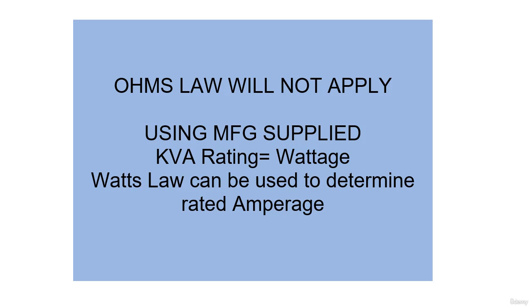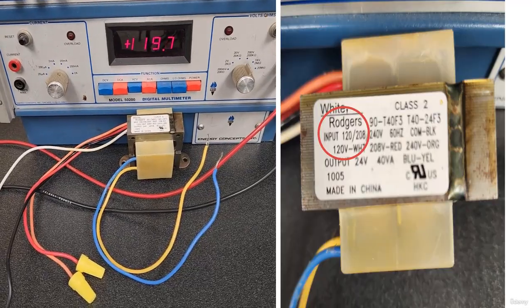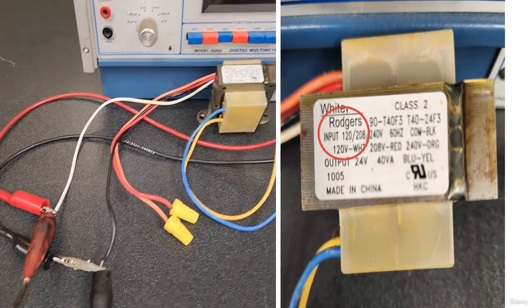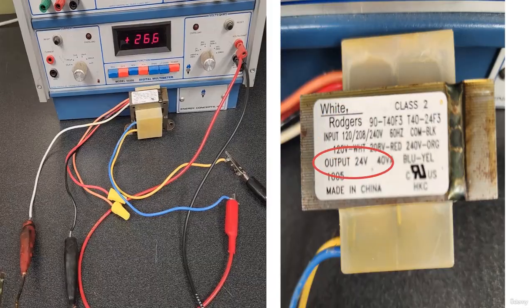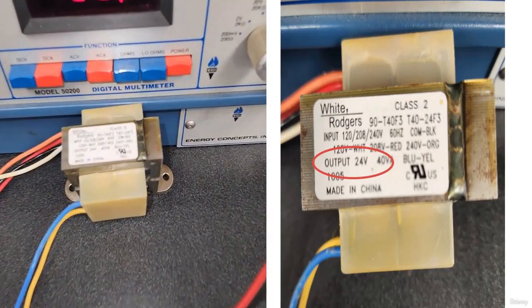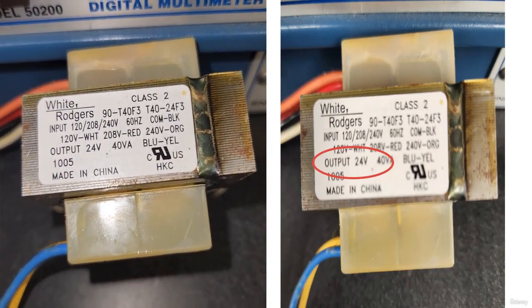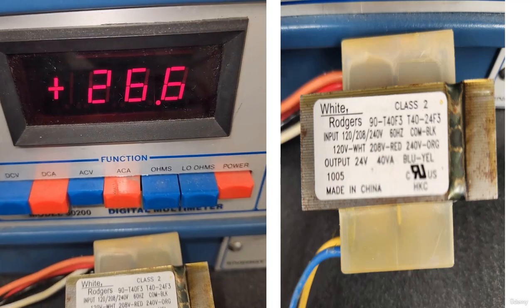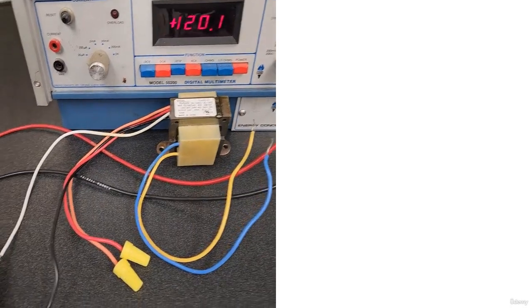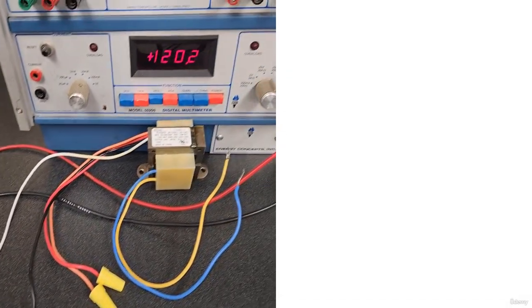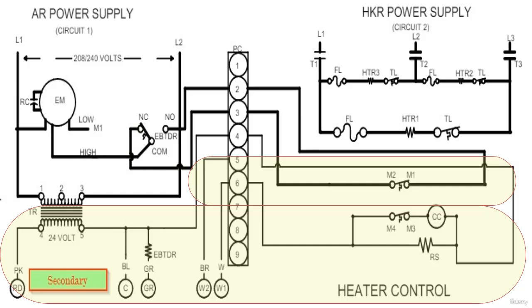We will not be able to use simple math to determine if it's correct without having a lot of data from the manufacturer. So the easiest way to check it is, do I have the correct input voltage and do I have the correct output voltage? Use your meter on the volt scale to test. Transformers typically do not fail on their own. Failure usually lies in incorrect input voltage or something on the secondary side shorted out, causing a high current flow through the secondary side of the transformer.